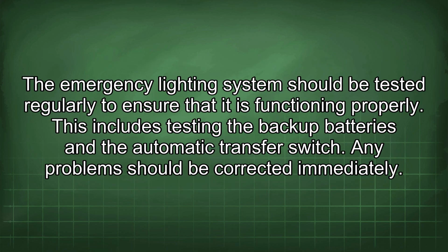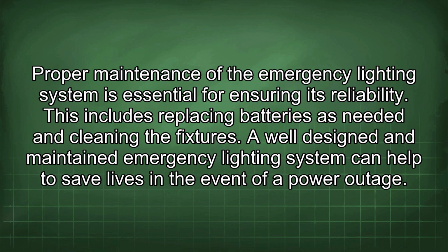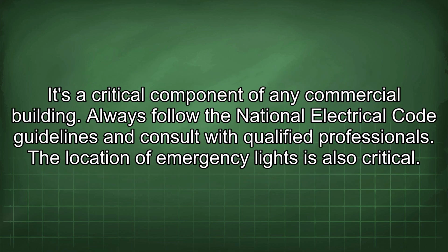The emergency lighting system should be tested regularly to ensure that it is functioning properly. This includes testing the backup batteries and the automatic transfer switch. Any problems should be corrected immediately. Proper maintenance of the emergency lighting system is essential for ensuring its reliability. This includes replacing batteries as needed and cleaning the fixtures. A well-designed and maintained emergency lighting system can help to save lives in the event of a power outage. It's a critical component of any commercial building. Always follow the National Electrical Code guidelines and consult with qualified professionals.